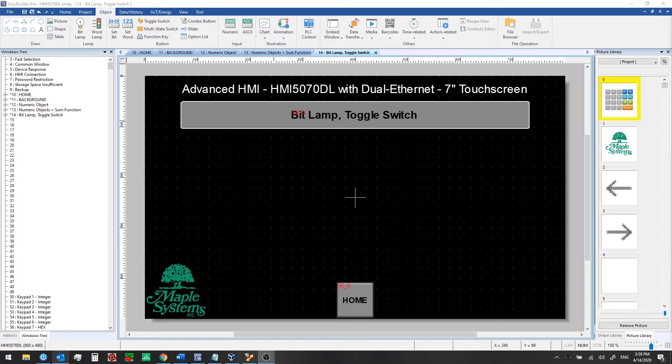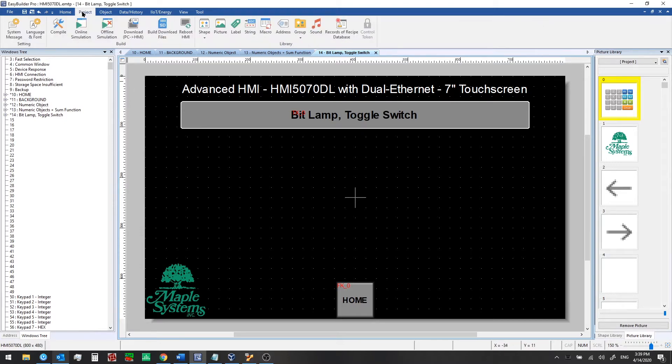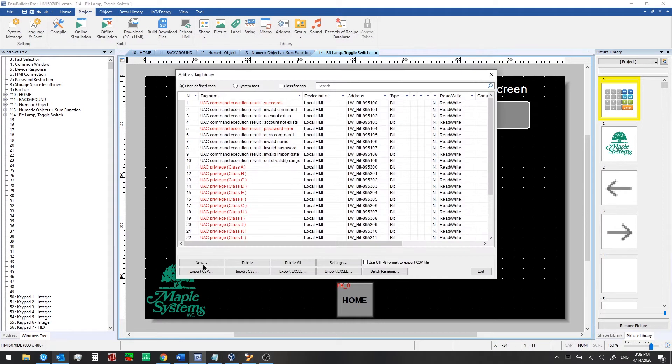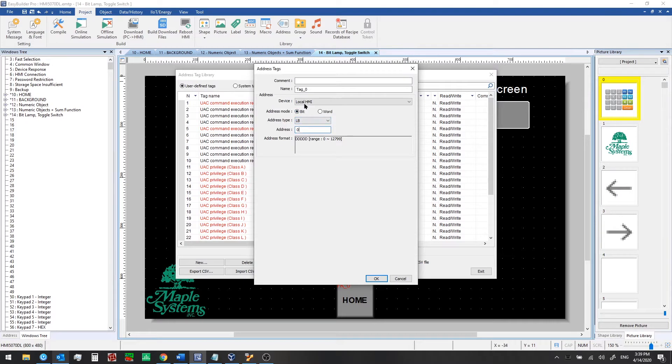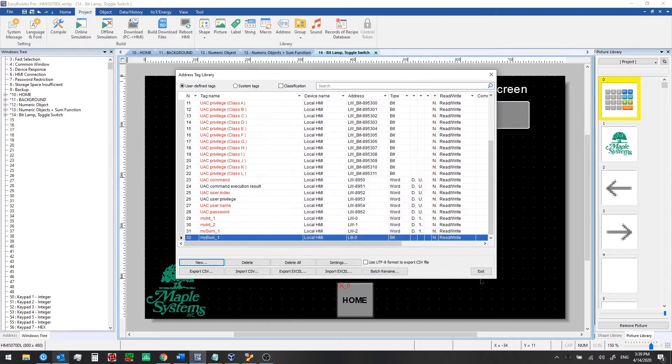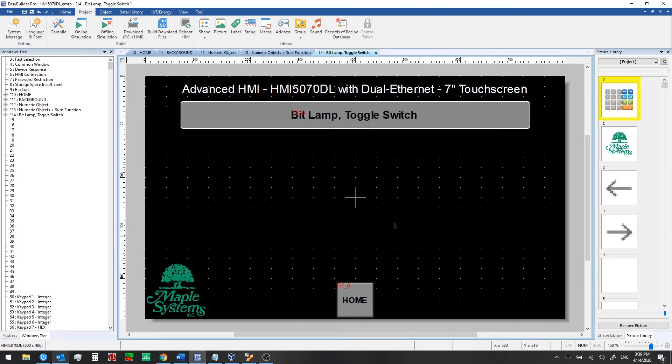To begin, we're going to create a new user defined tag. So we'll go to the project tab, click on address, select user defined tags, click new. This time we're going to select bit. This is for bit, boolean, or discrete memory in the HMI. And we'll use local bit zero for this. We're going to name this myBool1. And then we'll go ahead and click OK and exit.